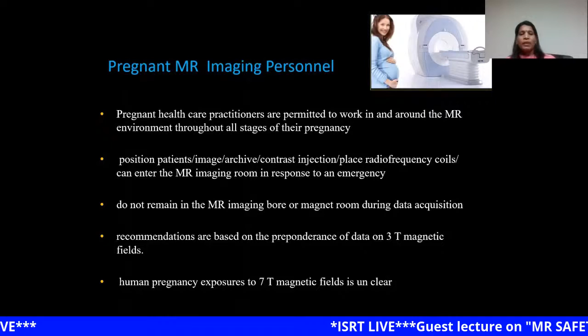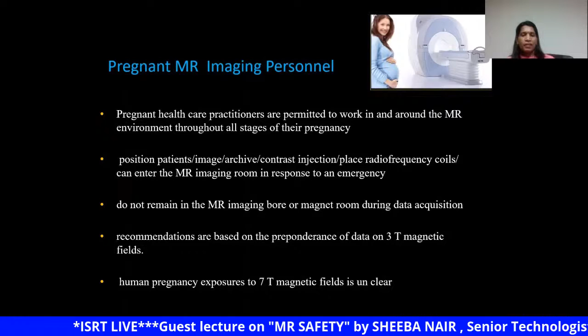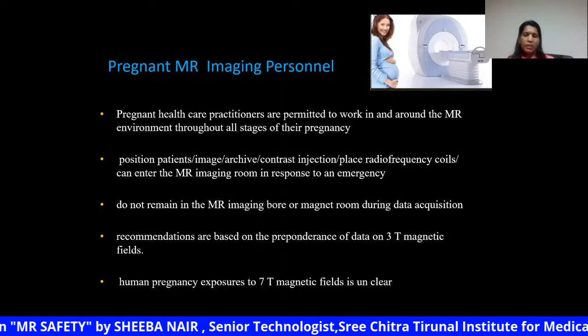They can work in 1.5 Tesla and 3 Tesla. Their safety at 7 Tesla is not established. But the only thing is that they should not enter the scan room while the scanner is scanning, that is, during the gradient switching. It is not recommended for pregnant personnel to enter the scan room.